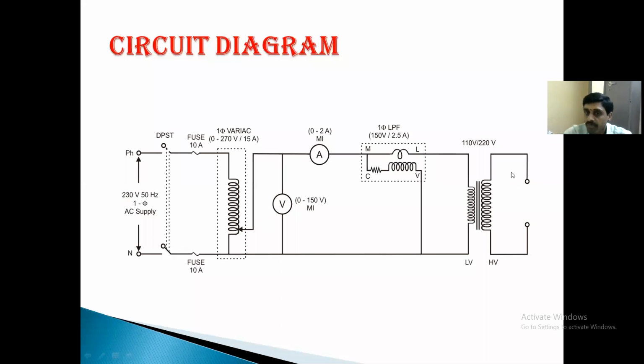Because in the primary side, we have to apply rated voltage for the open circuit test. If you take some 11 kV by 440 volts transformer, and take the primary as 11 kV and 440 as secondary, then you have to apply 11 kV on the primary side. So you have to connect voltmeter, ammeter, everything corresponding to that 11 kV. So it is not economical.